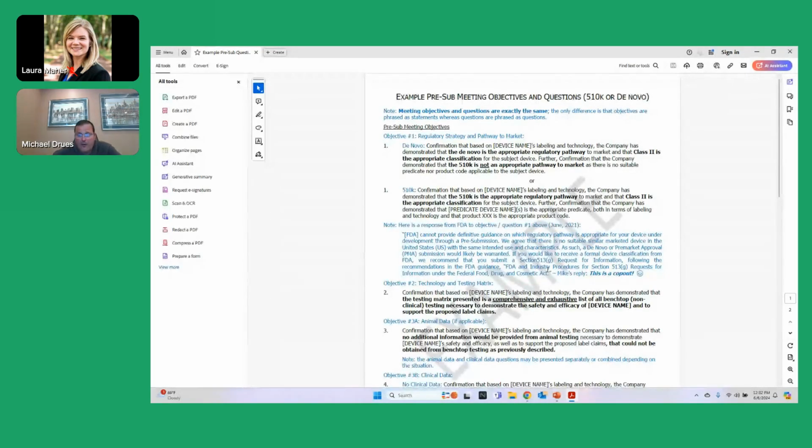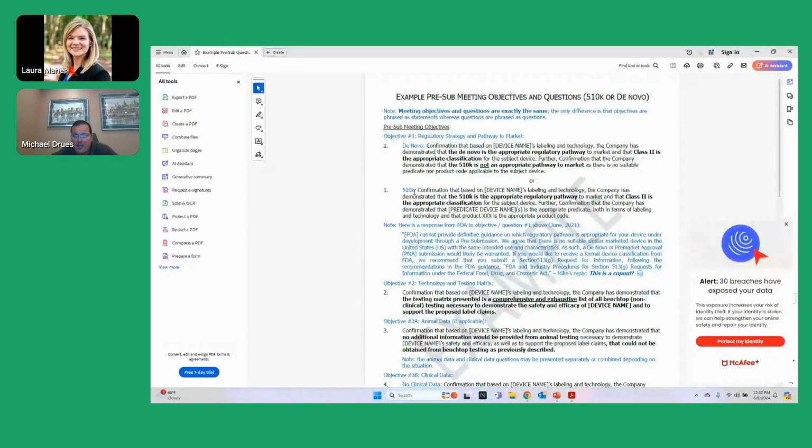I have some templates that I've developed that I share with my customers. I'm not going to make this available as part of the webinar, but I'll just show you a quick example of, for example, a 510(k) question. Confirmation that based on the device's name and the technology, the company has demonstrated that the 510(k) is the appropriate regulatory pathway to market, and a class 2 is the appropriate classification for the subject device. Further, confirmation that the company has demonstrated that the predicate is the appropriate predicate, both in terms of labeling and technology, and the product code is the appropriate product code.